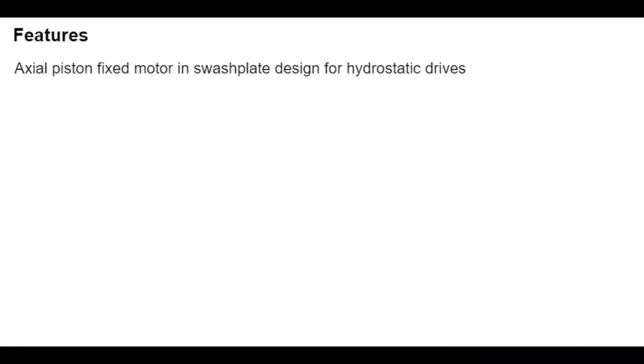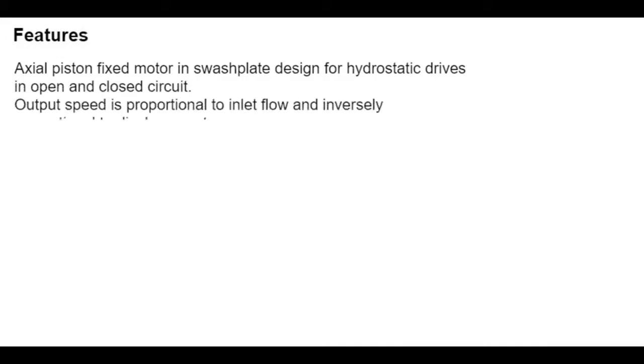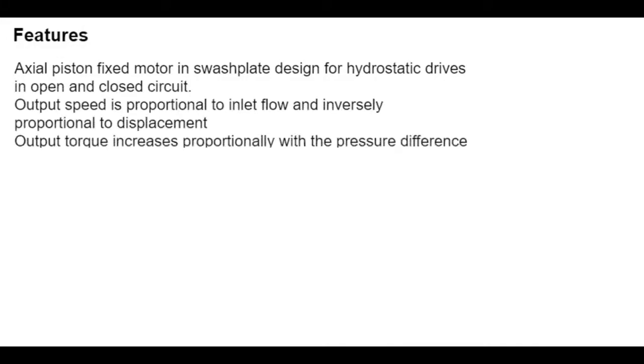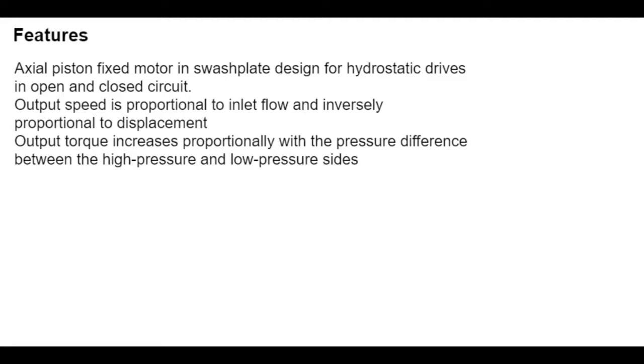The Rexroth axial piston fixed motor A4FM in swashplate design is specially designed for open-circuit and closed-circuit hydrostatic drives with minimal space. The fixed swivel angle makes the output speed proportional to the inlet flow and inversely proportional to displacement. Output torque increases proportionally with the pressure difference between the high-pressure and low-pressure sides. The hydrostatically mounted slipper pads also ensure long expected service life and optimal efficiency.